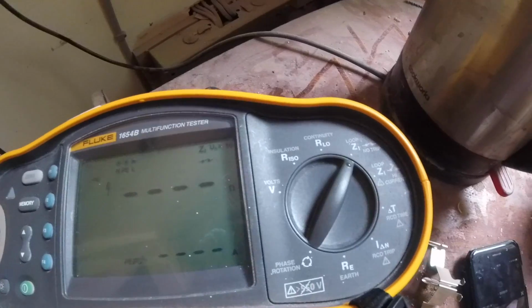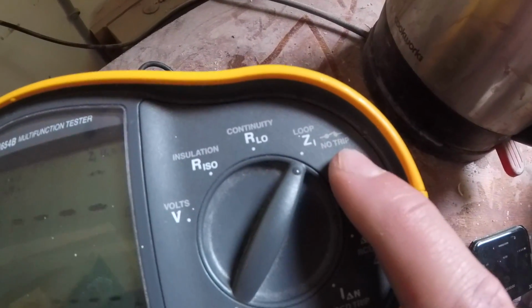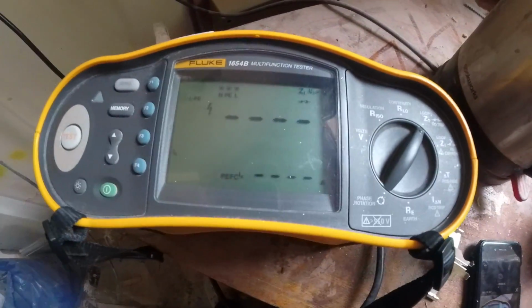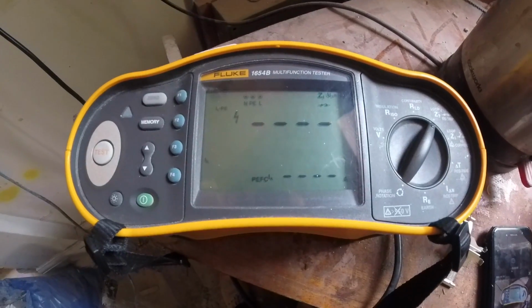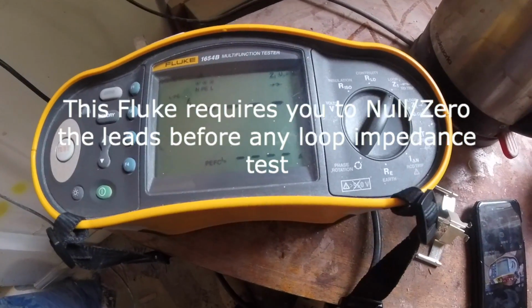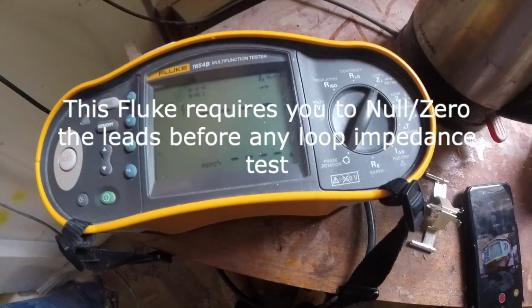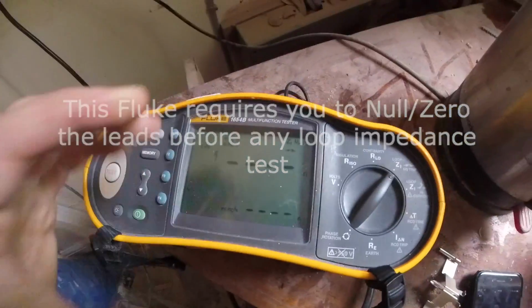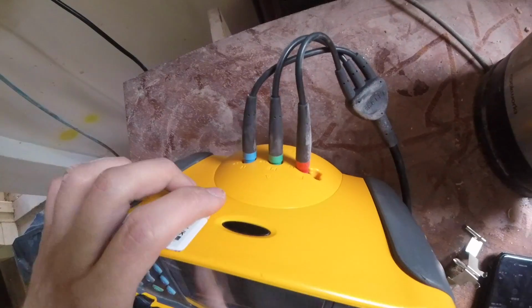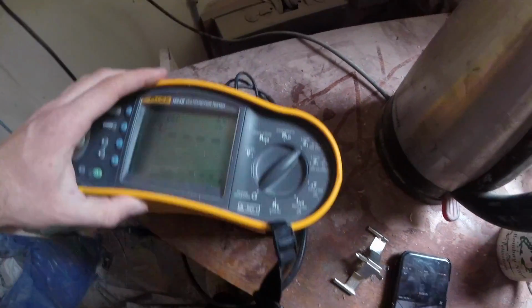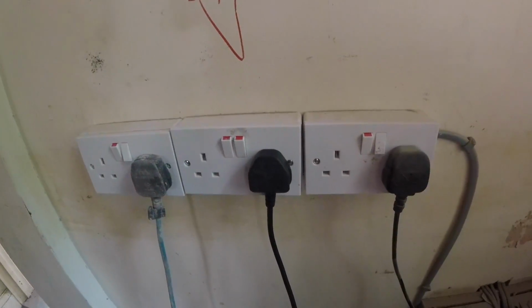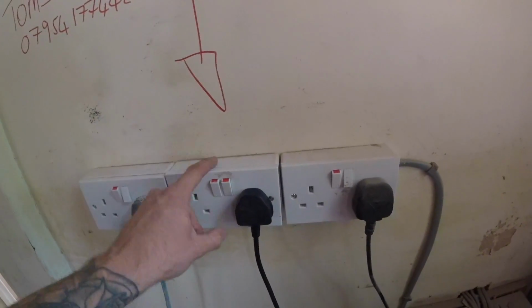Right, so I'm just going to show you the next test, which is the no trip earth loop test. So this is ideal for testing earth loop on circuits which have got the RCD on them. It won't trip the RCD, allowing you to get a reading basically. So all I'm doing for this test is I've got my plug adapter in the back plugged in, all three probes that goes round, and to one of my temporary plugs on, or sockets on the wall here.